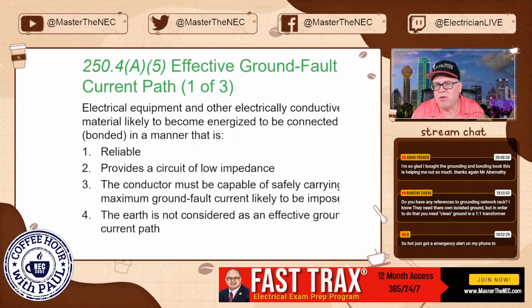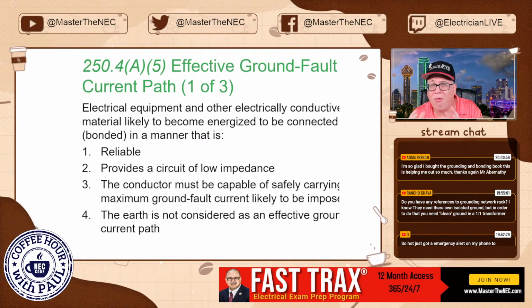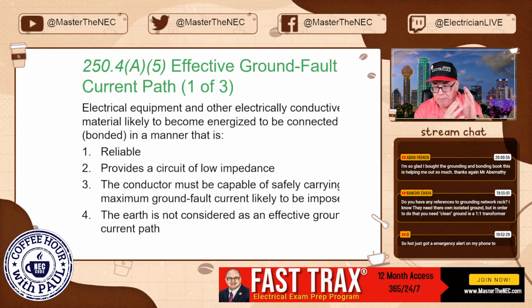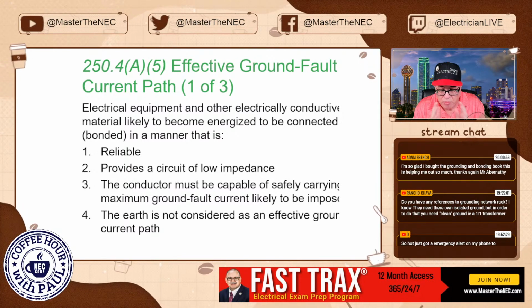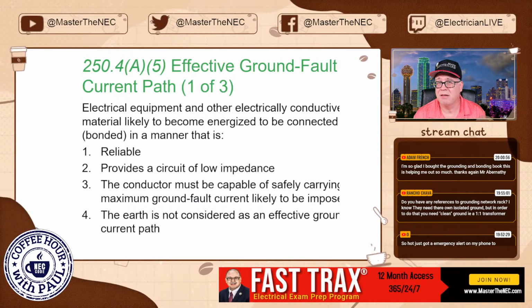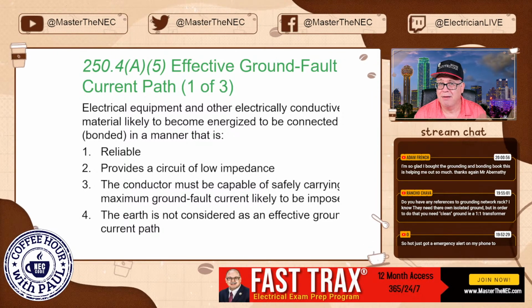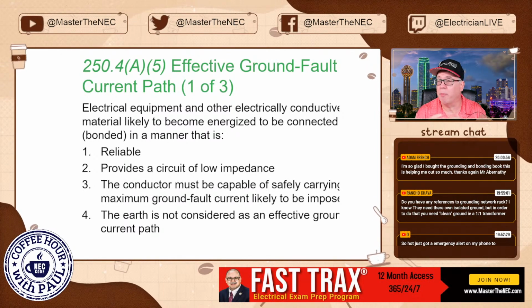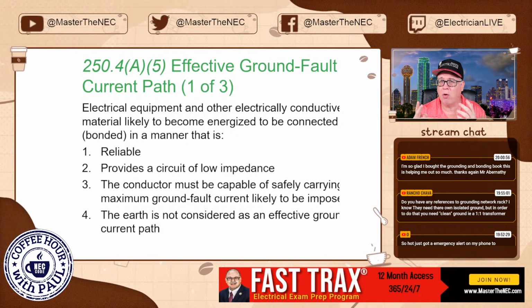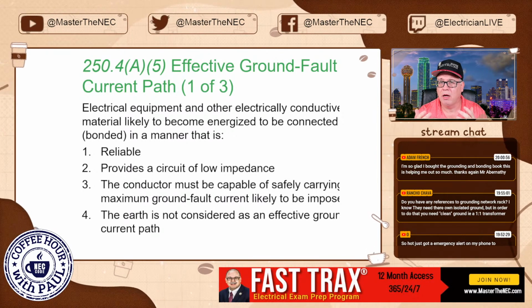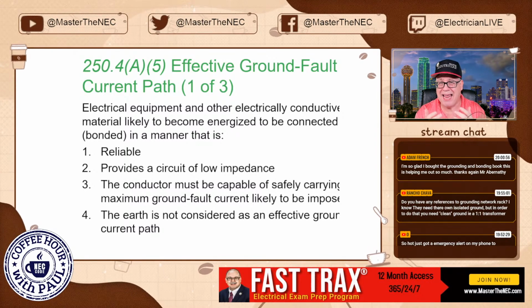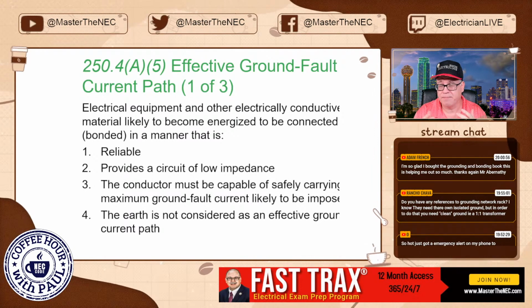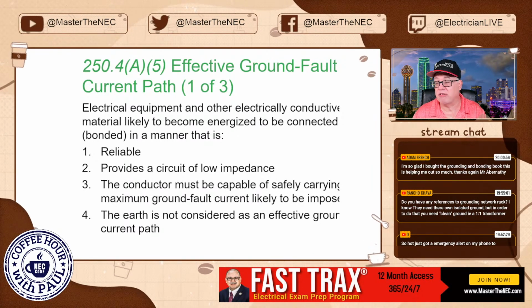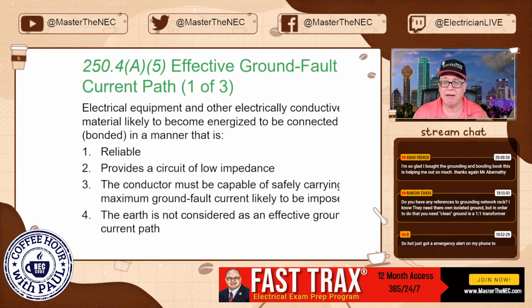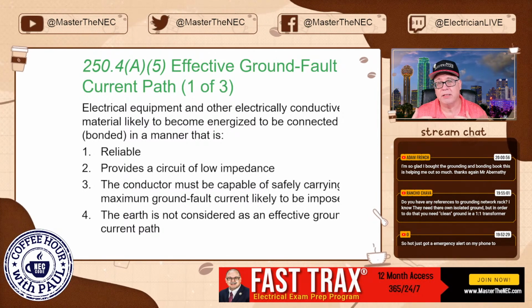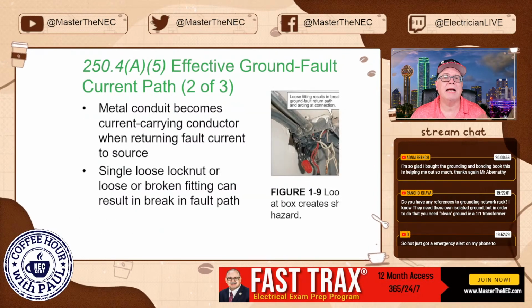Now, is it probable if the panel was sitting right next to the pole and the ground rod was right next to the panel and right next to the electrode for that panel and it was all right there? Maybe, depending on your soil conditions where you're at. But if you do the math, if you get 25 ohms in a perfect world for ground rods and you have 120 volts, you're only going to get about 4.8 amps if you use Ohm's law. Is 4.8 amps going to clear a 15 amp overcurrent device? No way. Never happen. Never happen. So it's a fallacy to think that way. So I told him, I said, well, you can do what you want, boo. But at the end of the day, somebody gets hurt, they're going to be calling me, and I'm going to come out there and I'm going to hang you. I'm just saying. All right.